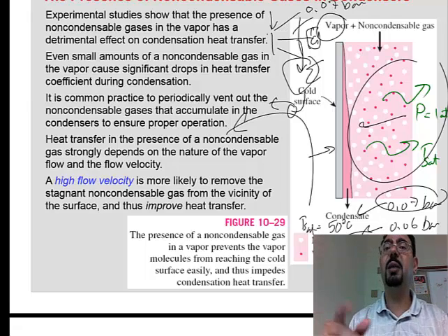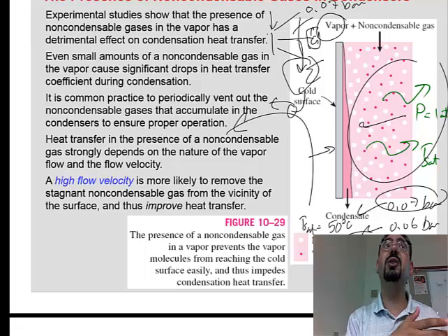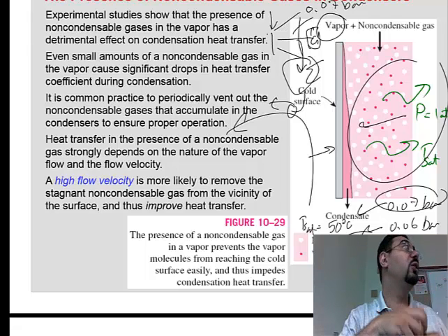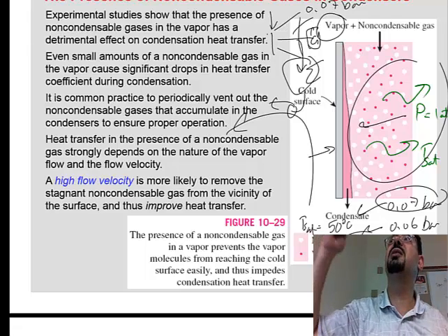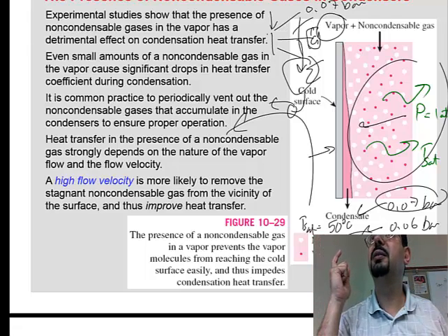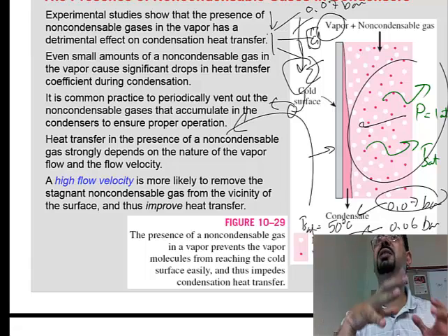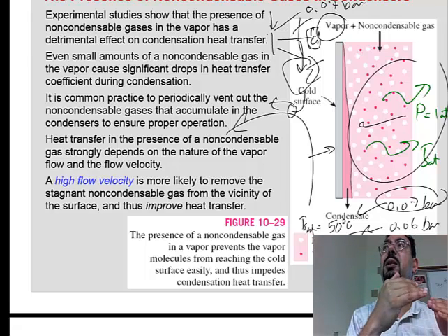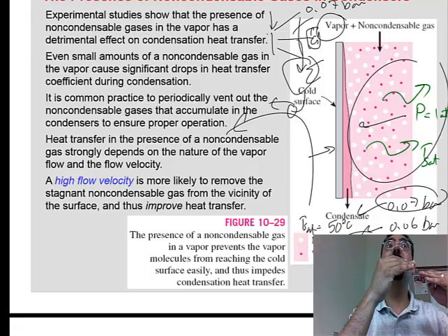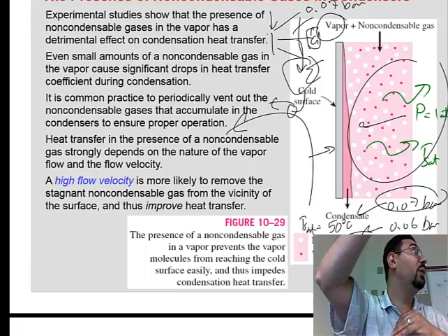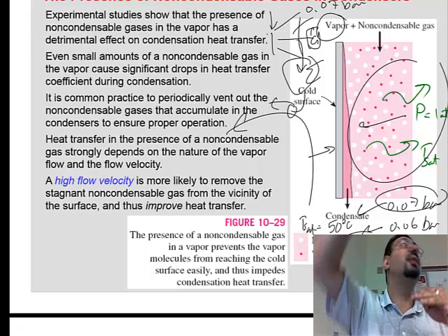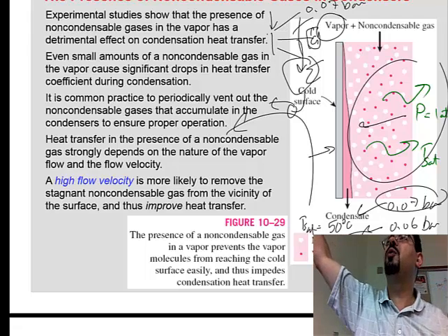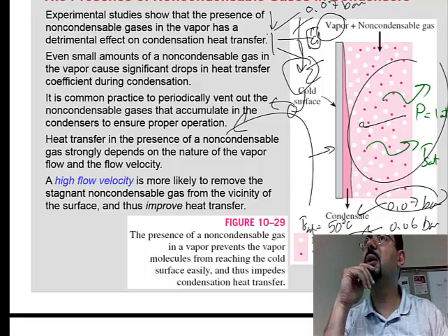So in the cycle, before they send that vapor into the boiler, they have a place that they call the deaerator, where you vent all this extra air. Alright? So the deaerator would be a place where the pressure is above atmosphere, higher. So they pump the condensate a little bit, and in a place where it's above atmosphere, they try to separate the water from the air, and they vent, and then the air would go from the top. Alright?